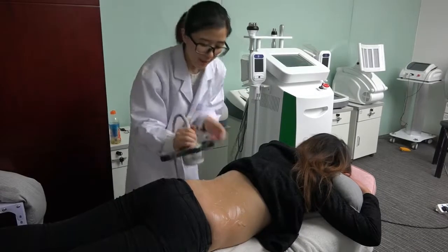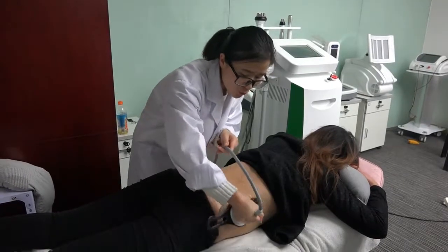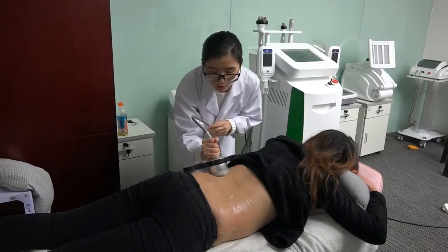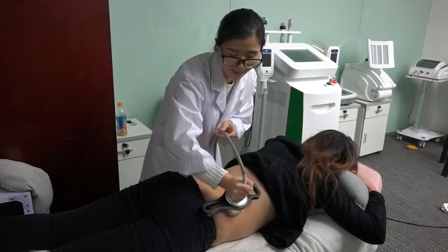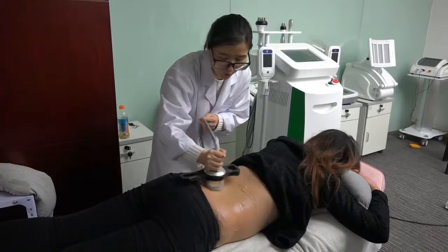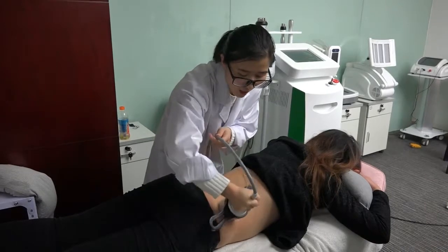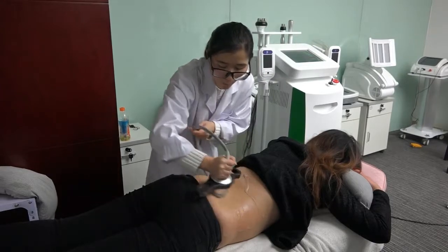One thing I would like to tell: after you press start to do treatment, please do treatment right away. Don't leave this handpiece under light condition. It means if you press start, you should start working right now, or it will make the handpiece broken.